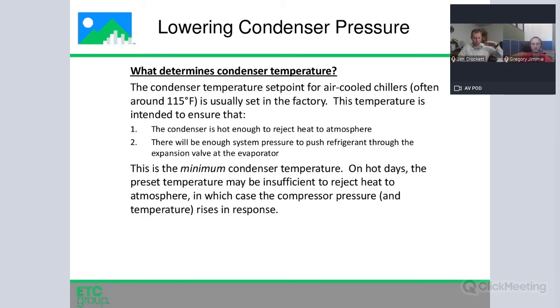So now we've talked about raising the evaporator side of the equation. Is there anything we can do to drop the pressure and the temperature of the high side? One thing that we found is that the condenser temperature of most air-cooled chillers comes from the factory set for about 115 degrees. And 115 degrees is hot enough to reject heat to atmosphere. You've just absorbed a bunch of energy from the building, and you've got to increase the heat of this energy high enough that it can be carried away by atmosphere. So if you're in Phoenix and it's a 115 degree day, 115 degrees in your condenser is not going to allow you to transfer any heat out.